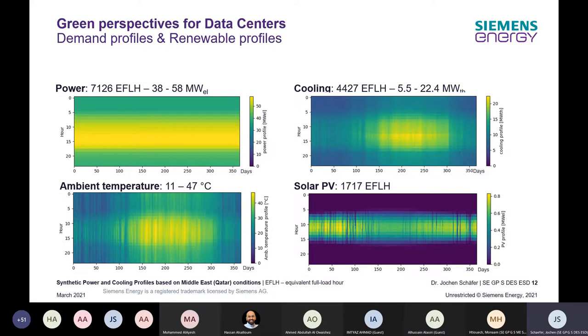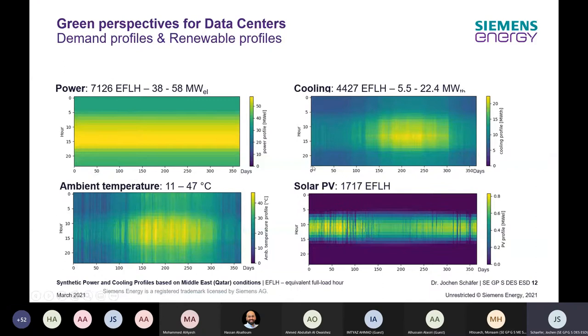For this type of analysis, it's important to use hourly resolution for a representative year to capture fluctuations in demand and generation profiles throughout the day and year. For example, the power load profile shows fluctuation throughout the day while remaining relatively stable across the year. The cooling demand shows changes both throughout the day and throughout the year, as do ambient temperature and solar PV potential.